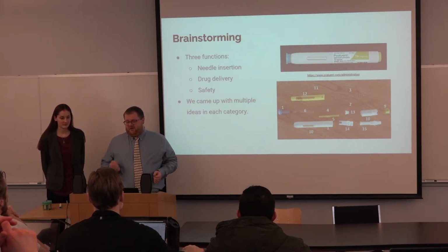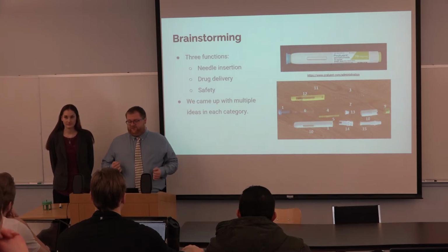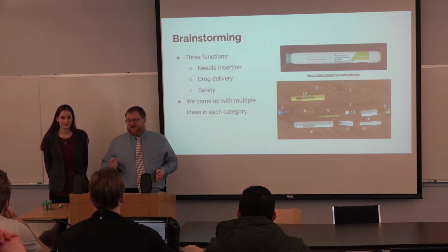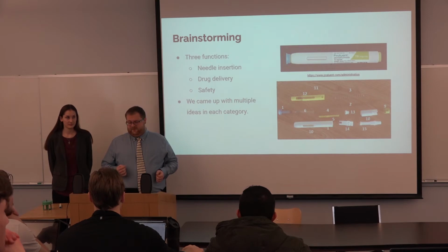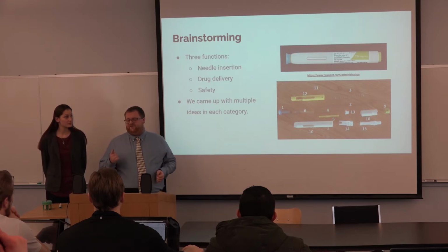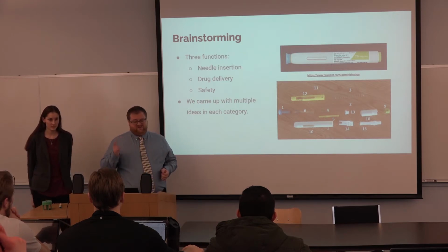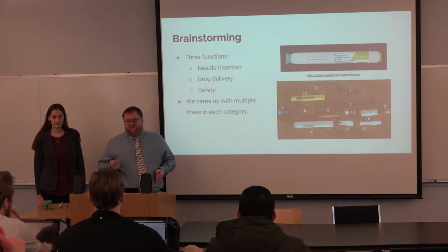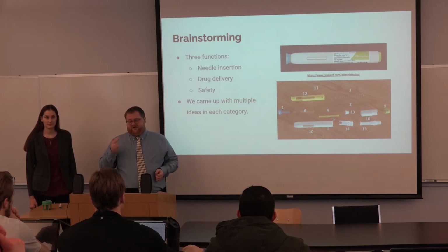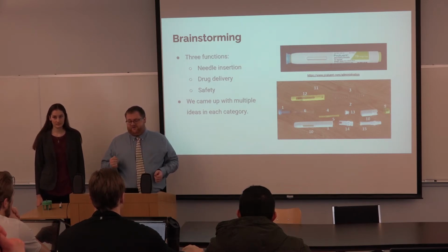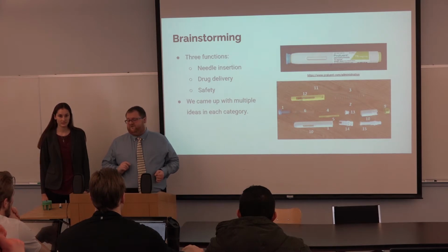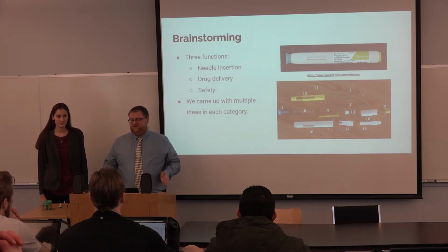One of the things we learned is that what we assumed to be a relatively simple device was actually a lot more complicated. We identified 3 main functions. First, the needle must be inserted with enough force to penetrate the skin at the correct depth. Second, the drug must be dispensed completely with a constant force. And third, the auto-injector must also have at least one safety mechanism to prevent patients from accidentally injuring themselves with the needle.